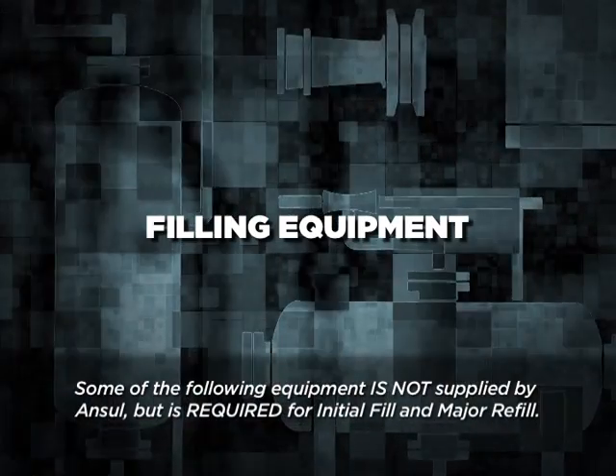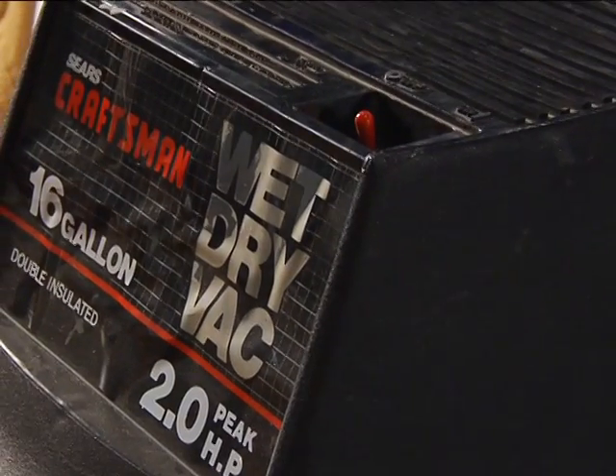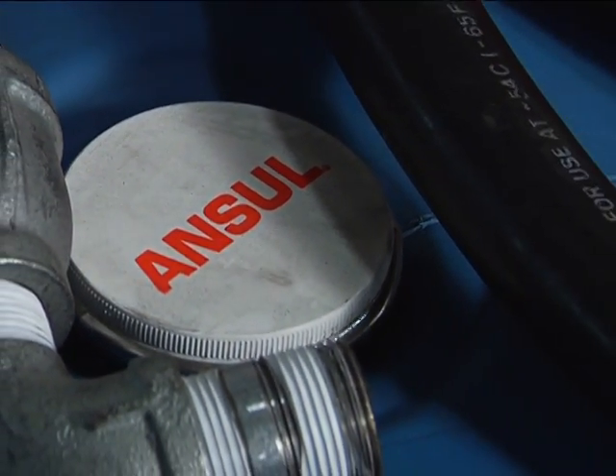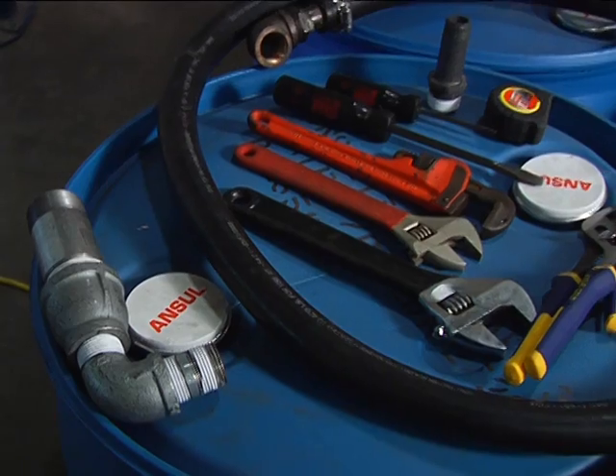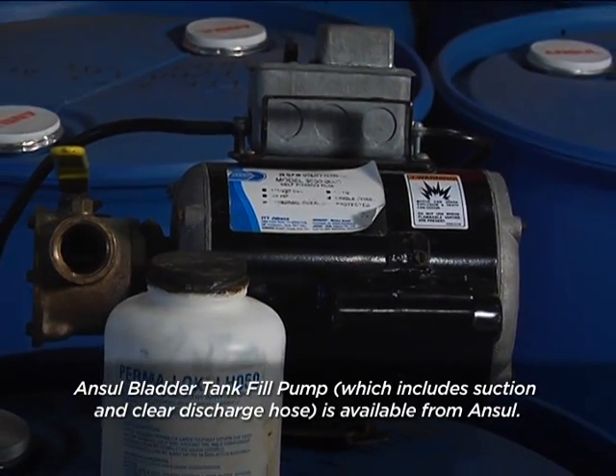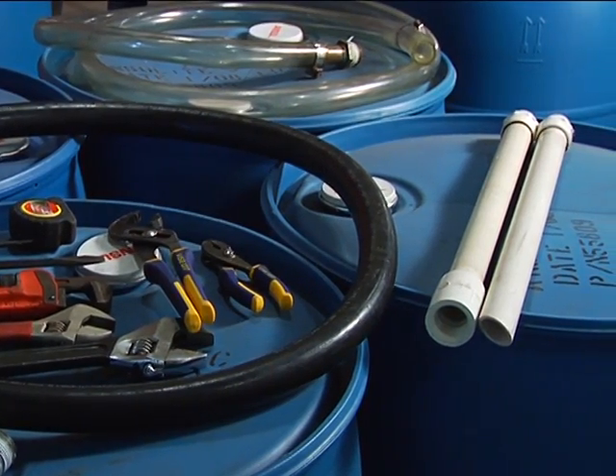When performing an initial fill, or a minor or major refill for an Ansul bladder tank, you must first have the correct equipment. You'll need a wet-dry shop vacuum with a 2 horsepower motor or larger, along with appropriate pipe fittings and duct tape to connect the vacuum hose to the 1-inch NPT tank shell vent valve. You'll also need a concentrate fill pump capable of 25 GPM maximum output at 15 PSI (1.03 bar), a pump suction and discharge hose, a 2-position ball valve, and all appropriate fittings for connecting to the 1-inch NPT bladder drain fill valve.